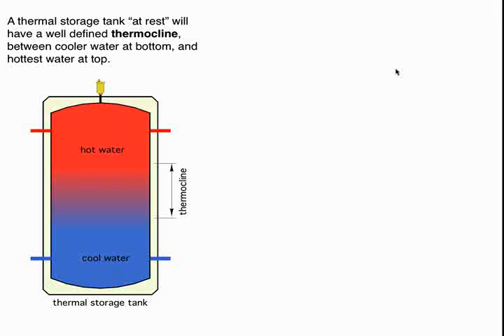Okay, temperature stacking. This is a kind of a unique strategy. I'll try to go through it quickly. When we have a pellet-fired boiler, one of the things we really want to do with a pellet-fired boiler, and this would apply to a wood chip boiler as well, we want to keep that boiler operating for a nice long cycle. Think multiple hours. So we're going to turn on that boiler based on a condition in the buffer tank, and once we turn that pellet boiler on, we're going to let it run until we basically fill this tank up with significantly higher temperature water. We might turn the pellet boiler on when a sensor, let's say at the midpoint of the tank, gets down to about maybe 120 degrees Fahrenheit.